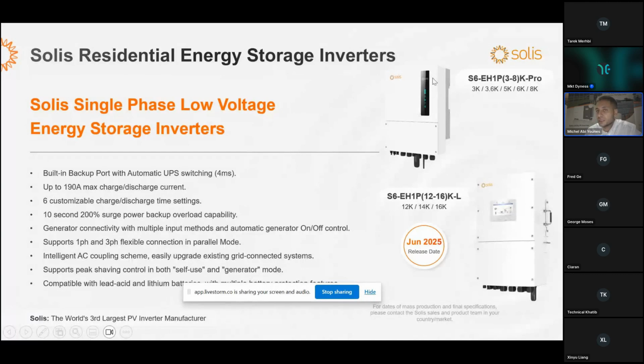Both the settings of the both inverters can be accessible through online and through Bluetooth. The additional feature of the Plus, which has a screen, is that the settings can be set directly through the screen. The main feature are the automatic switching time is typically 4 milliseconds. So it is more like a UPS, similar to the UPS switching time.